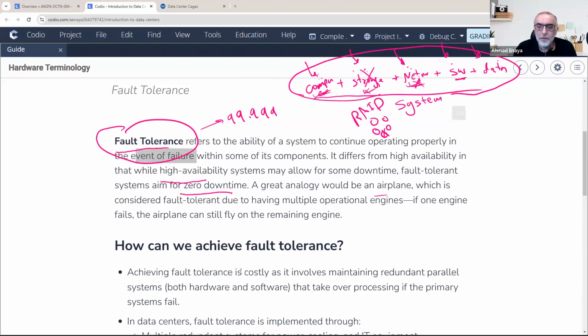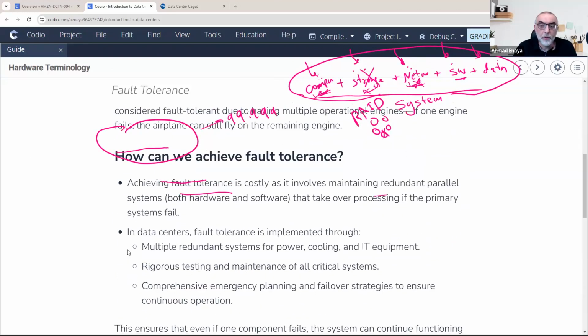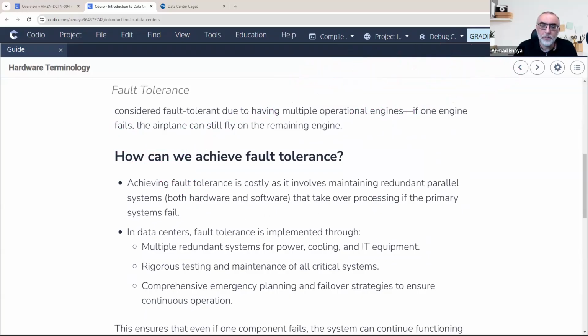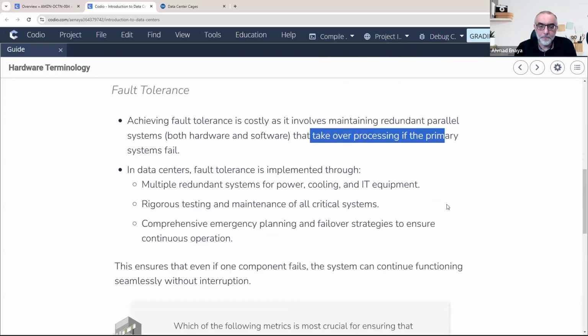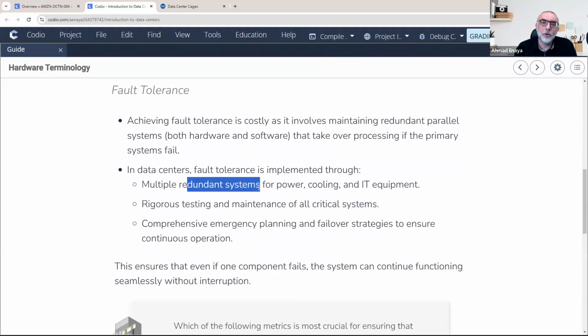This seems to be costly because we need to have parallel components. All the components, hardware and software, should have redundant parallel components running all the time and should take over processing if the primary system fails. So how do we achieve fault tolerance in a data center? Typically, we need to have redundant systems, not only for the servers and storage, we need to have also redundant power supplies, power system, redundant cooling, redundant IT equipment. We need to have testing. So having redundancy is not enough.